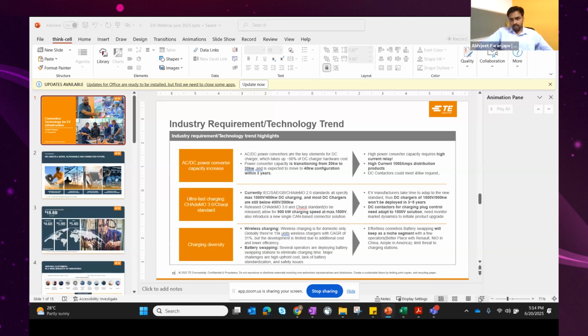Now, if you take this thesis, what are the connection technologies that are needed? First is high current relay needed for such power converter capacity increment. Second is high current 1000 ampere distribution products, which are UL certified, IEC certified, and also IP20 products, because of the installation and maintenance needed in such infrastructure. The third is DC contactors, currently available at 10 and 15 kilowatt, which need to be expanded up to 40 kilowatt as and when required.